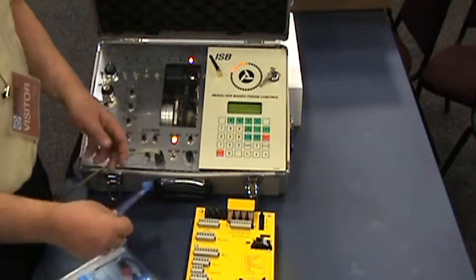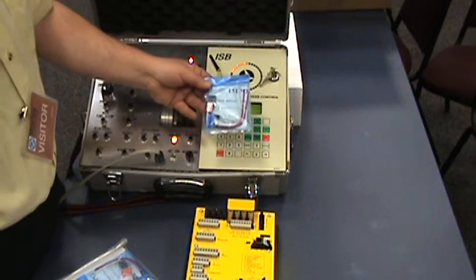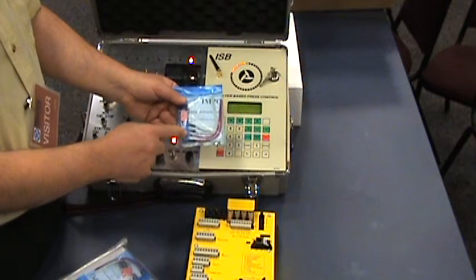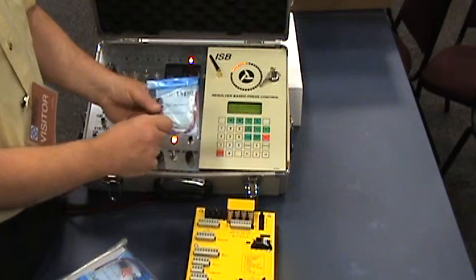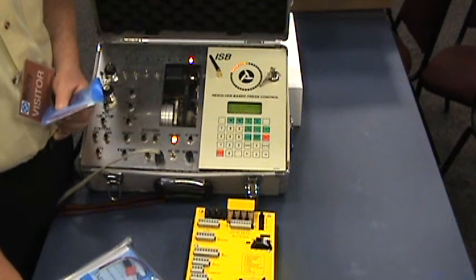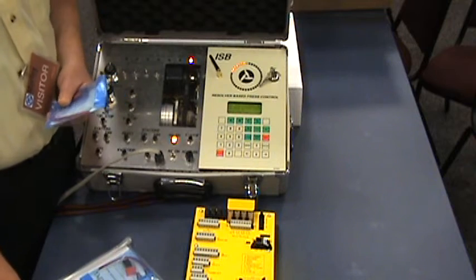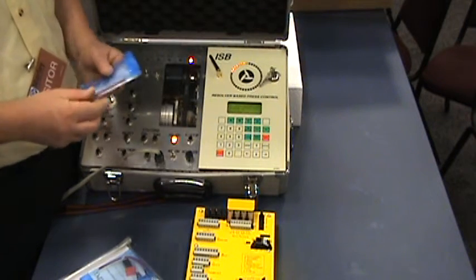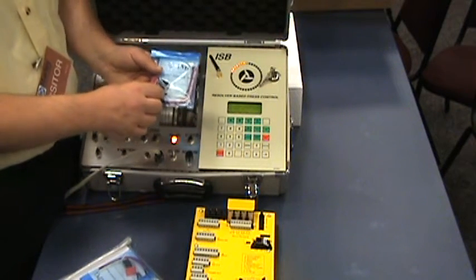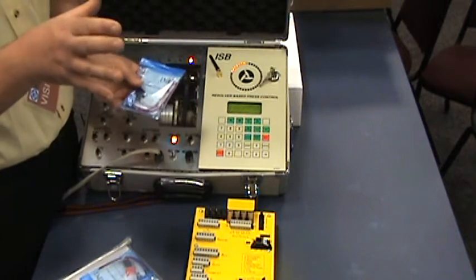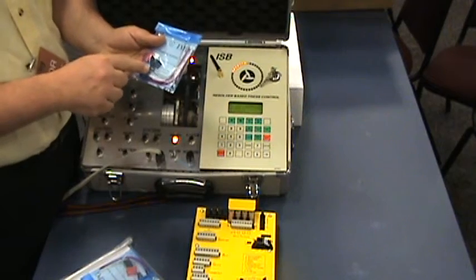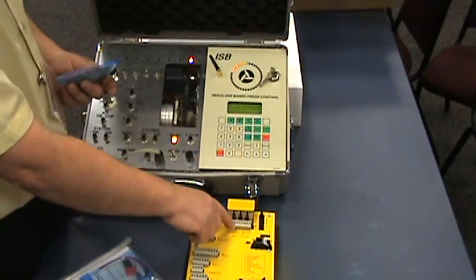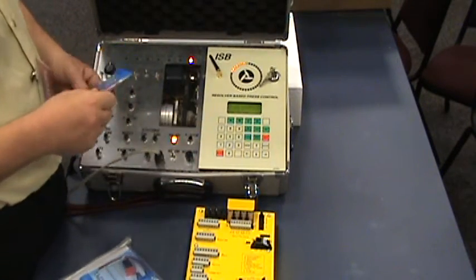But you are powering that with the output relays in this device. So when we supply the unit, every RBPC comes with this little bag in the box. And what you see are these two blue devices are called quench arcs. These need to be installed across any inductive load that you're turning on and off every stroke. And of course the safety valve is the biggest inductive load on your press. Every time you engage the clutch and disengage the clutch, that relay is turning on and off. So make sure you install these right at the safety valve.